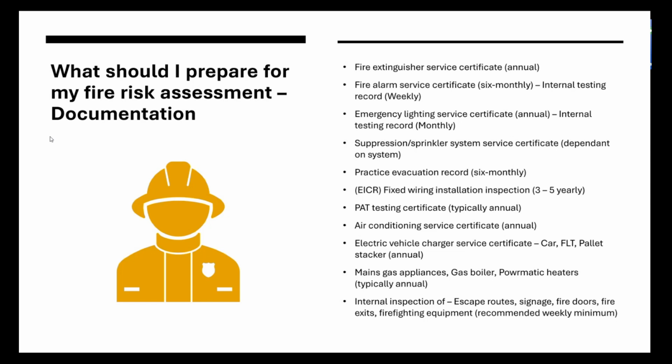Practice evacuations. So these are required as a legal requirement, should be done 6 monthly. However, they should be performed more frequently if you have any significant changes to your organisation, you change the layout, anything like this. We should be looking at redoing a practice evacuation, as differences in routes, changes in layouts can all affect our evacuation, and we need to know before the time that is an actual evacuation that it works. So practice evacuations must be recorded in the fire logbook. As much information as you can. That's all I'll say on practice evacuations. As much information on that evacuation as you can in that logbook.